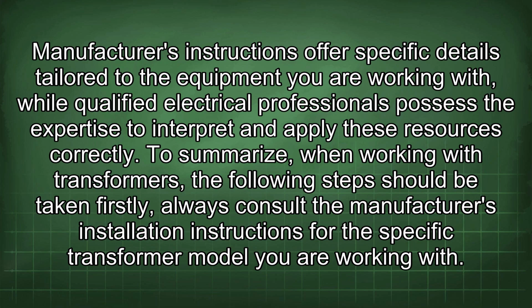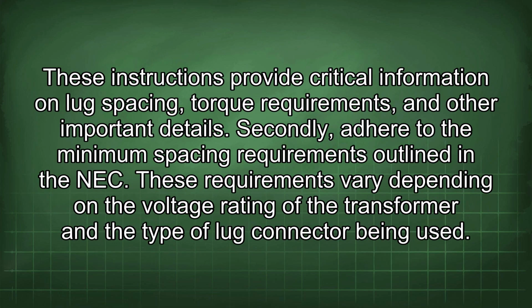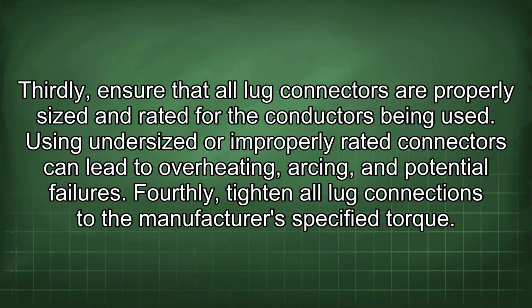To summarize, when working with transformers, the following steps should be taken. Firstly, always consult the manufacturer's installation instructions for the specific transformer model you are working with. These instructions provide critical information on lug spacing, torque requirements, and other important details. Secondly, adhere to the minimum spacing requirements outlined in the NEC. These requirements vary depending on the voltage rating of the transformer and the type of lug connector being used. Thirdly, ensure that all lug connectors are properly sized and rated for the conductors being used. Using undersized or improperly rated connectors can lead to overheating, arcing, and potential failures.